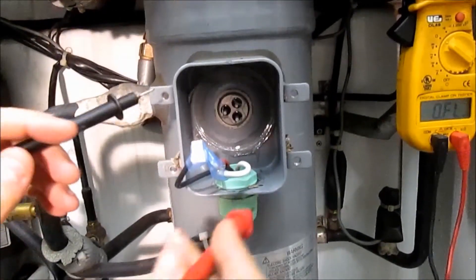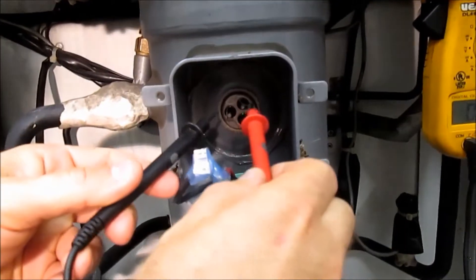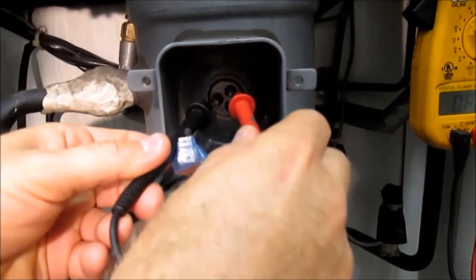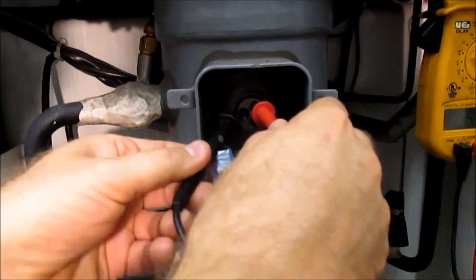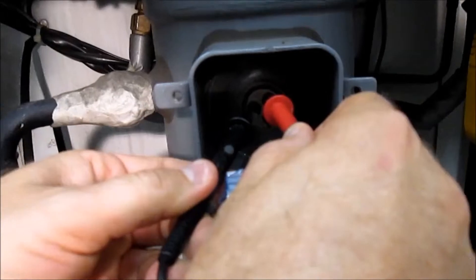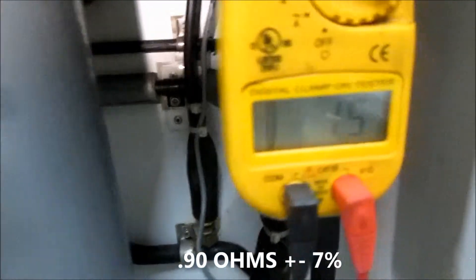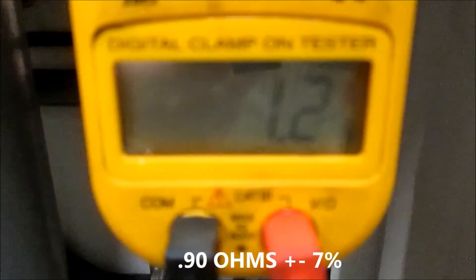Okay, we're going to check the resistance on the compressor. So we go here, and that should be around 0.9 ohms, 1 to 0.9. Okay, next one.